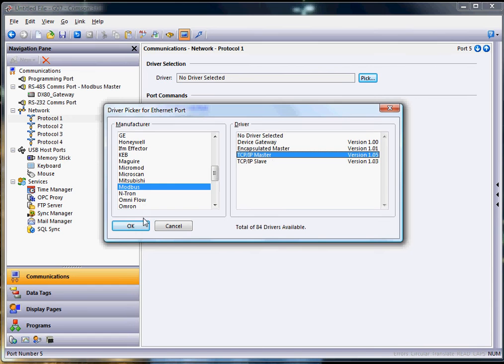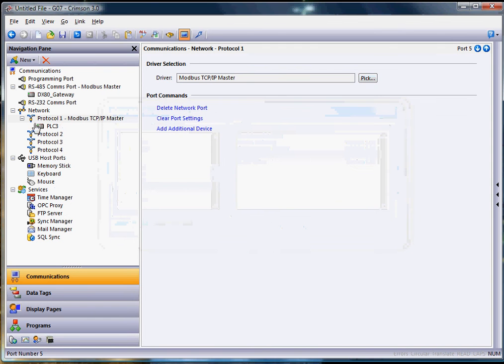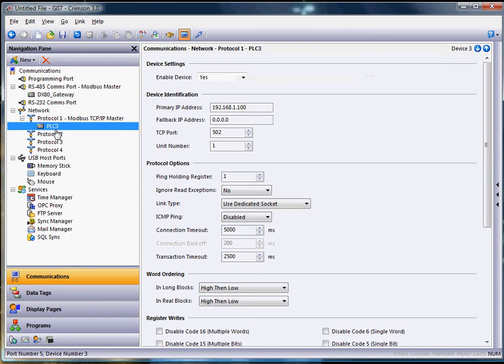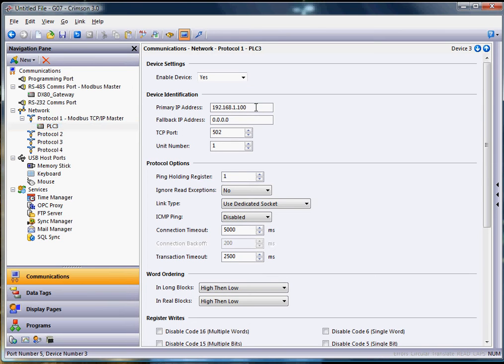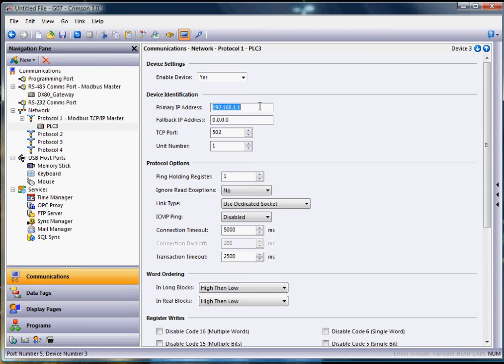Over here on the left where it says PLC3, when you click on that, that's going to be the IP address or the device on the ethernet connection. So you want to set up the IP address here to make sure that's correct. Most of the Banner wireless default would be 192.168.1.1, so I'll change that there. Don't forget folks, whenever you hit the keyboard, remember to hit the enter key or tab to make sure that particular field sticks.